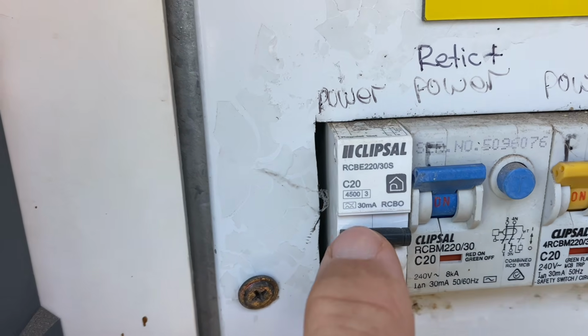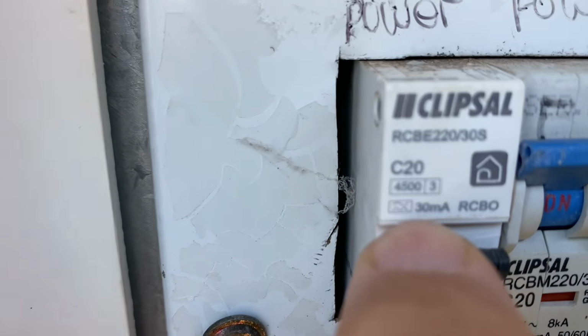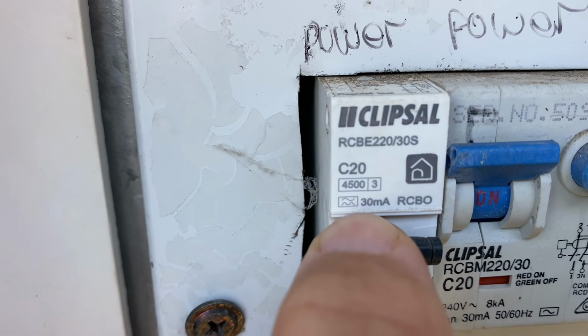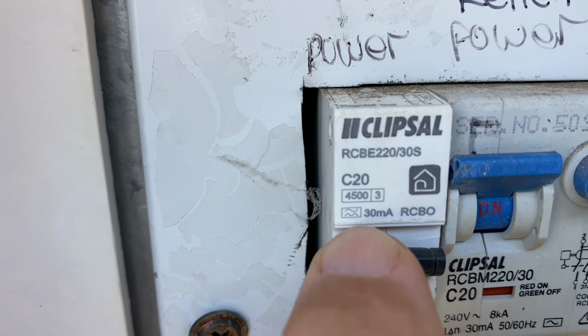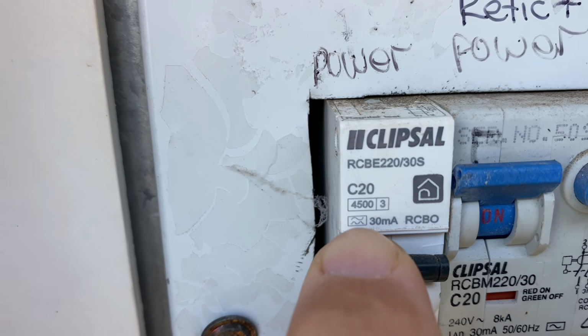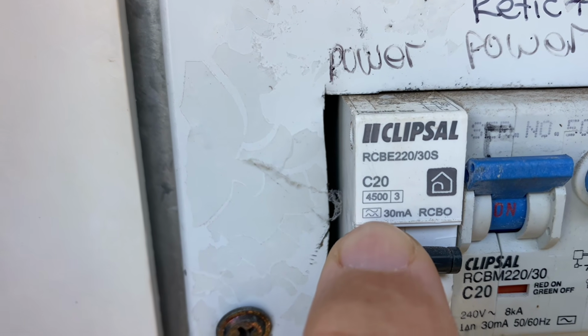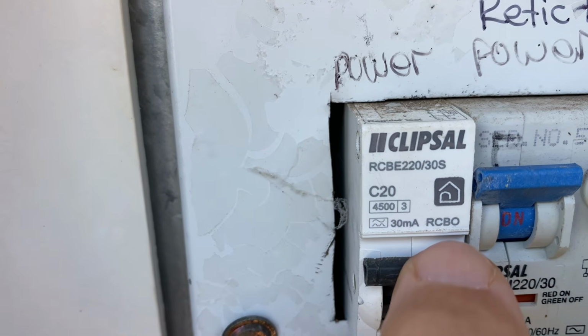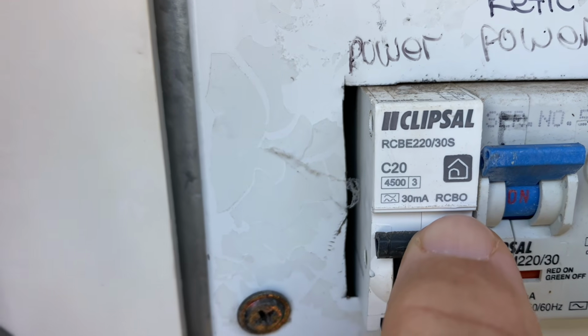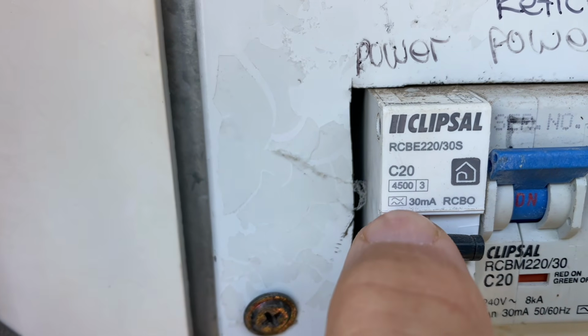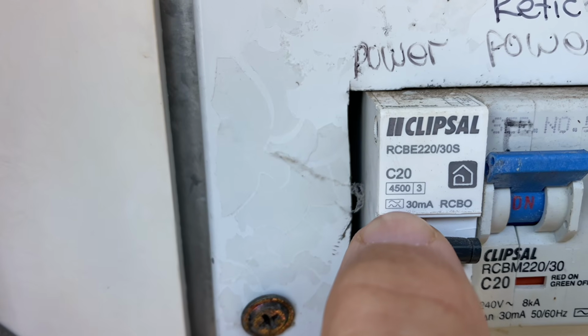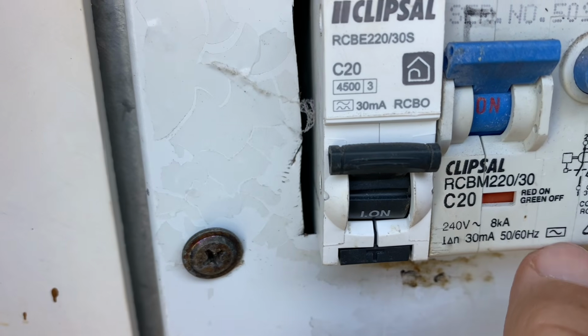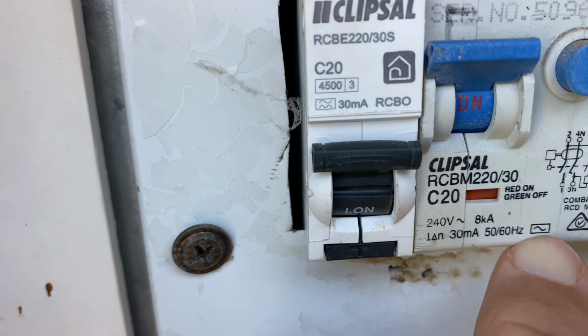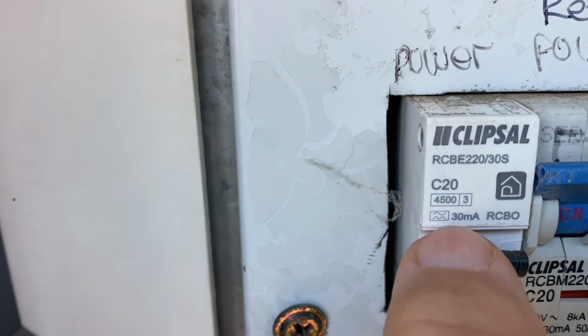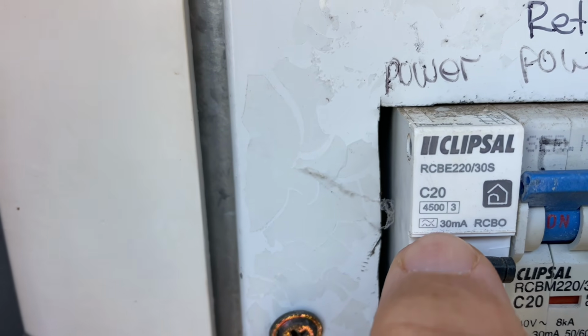And then if we move to this newer one here, let's try and go in nice and close. You'll see there's that mark there. Now that is our type A RCD, or as I said before, RCBO. So that's what we're looking for, is that symbol there, not that symbol there. That one is type AC, that one is type A, and it's the type A that we want.